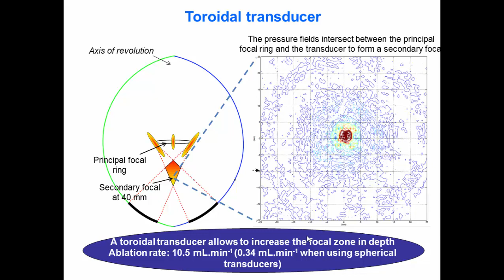These are the parameters we used for developing the transducer. The central frequency was set at 2.5 megahertz. The radius of curvature was 7 centimeters in order to treat the deepest regions of the liver. The diameter is 7.3 centimeters in order to hold the device by hand by the surgeon. The radius of the focal zone was set at 15 millimeters, and the transducer is divided into 32 concentric rings of equal surface in order to steer the beam electronically.